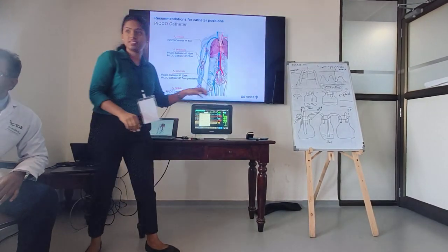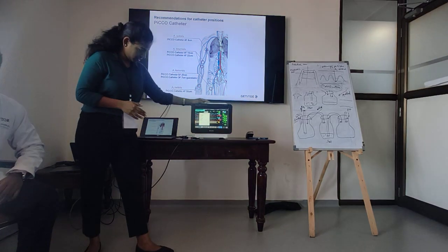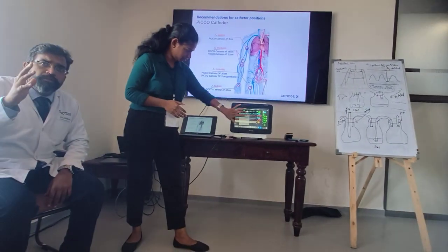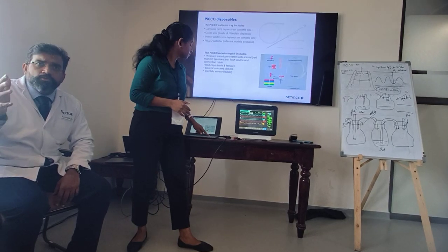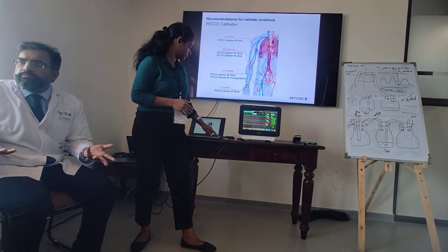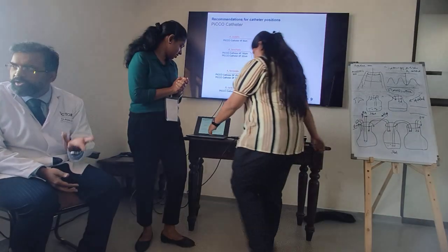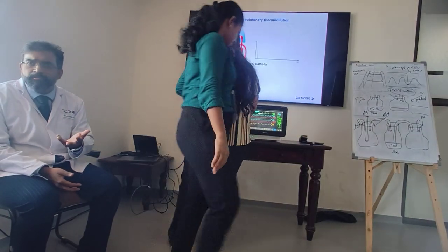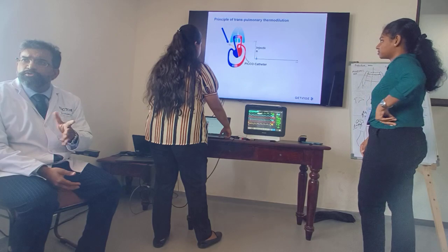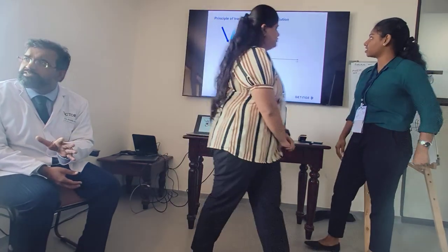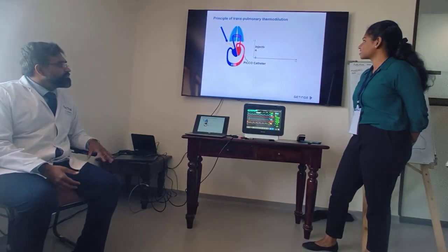So now you must also understand कि जब तुम inject कर रहे हो, don't inject it fast. Don't inject it very slow. Because if you inject it fast, it will go fast inside. You inject it slow, it will go slow inside. It might change the characteristics. So on an average, you should finish the injection in 7 to 8 seconds. Something like that. Okay?